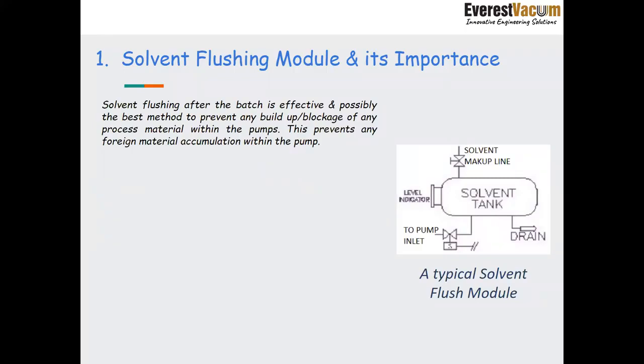Now what happens in the process when we are into certain applications? The carryover vapor, the product along with the solvents will come up into the dry screw vacuum pump along with the non-condensable load as well. So it will slowly and gradually start accumulating inside the pump. And if it is not cleaned after certain operation, if it is a continuous process after certain hours, or in batch application after certain batches, the accumulation would be so much that it will ultimately lead to the seizure of the pump. So that is why we need to clean out the pump, and it is recommended to be used with inlet purge for most effectiveness.